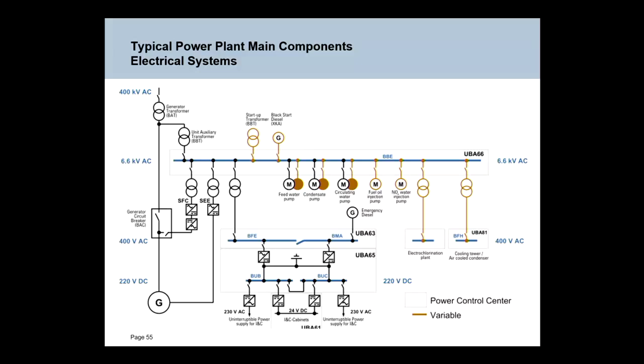Once you get much bigger than that, then you go up to higher voltage levels so the conductor size can shrink, okay, for higher power. And the largest motors in a power plant will be of the order of between 12 and 14 megawatts in a big coal-fired power station, that sort of size. So they're quite big motors.